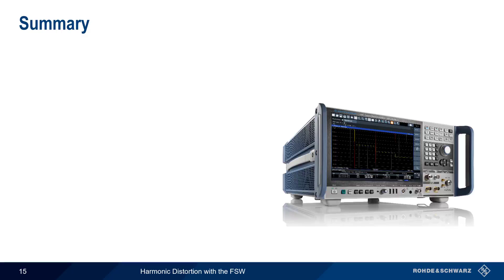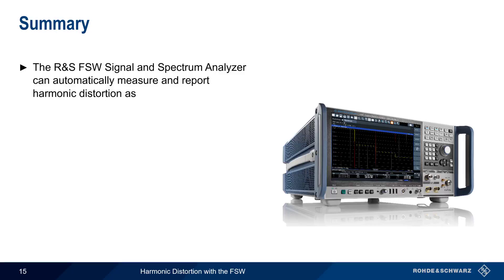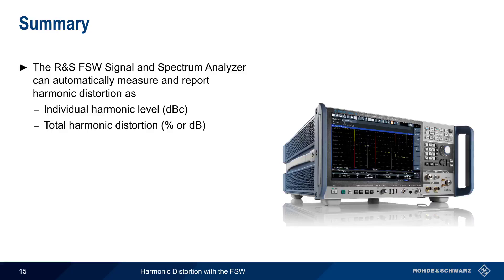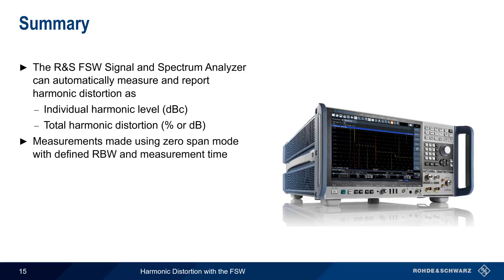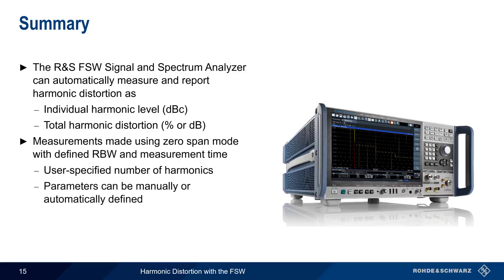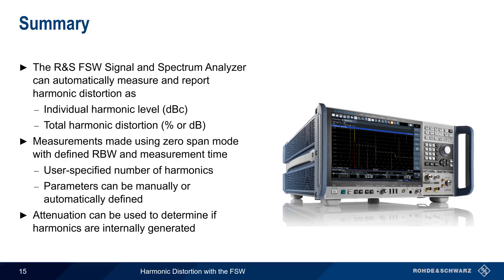The Rohde & Schwarz FSW series of signal and spectrum analyzers can automatically measure and report harmonic distortion, both for individual harmonics as well as total harmonic distortion. Harmonic distortion power measurements are made in zero-span mode using a configured resolution bandwidth and measurement time. In most cases, the user only needs to specify the number of harmonics of interest. Note that attenuation can be used to help determine if the measured harmonics are being generated within the spectrum analyzer itself. This concludes our presentation. If you'd like to learn more about spectrum analyzer measurements or the FSW, please see the links in the video description. Thanks for watching.